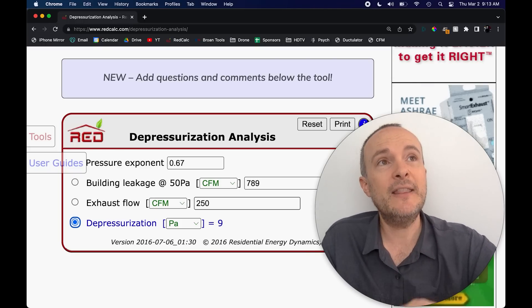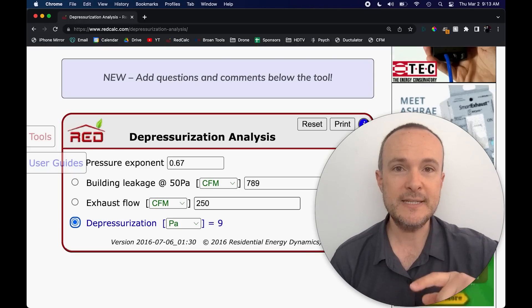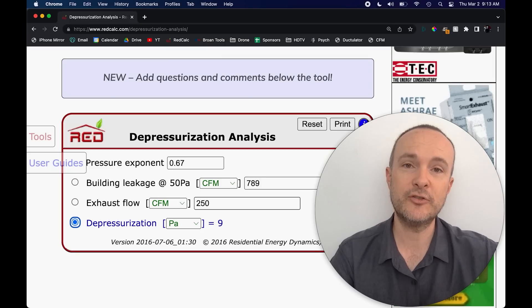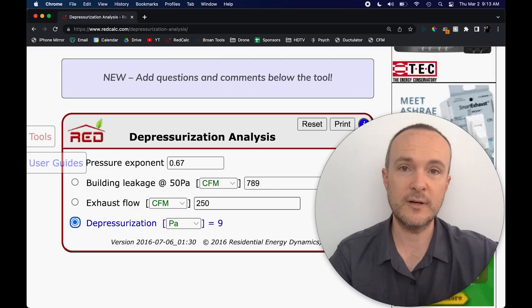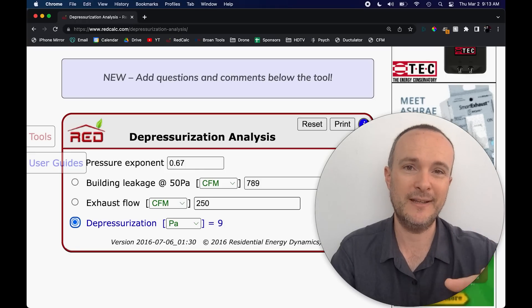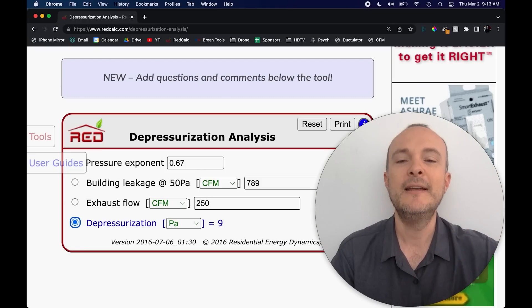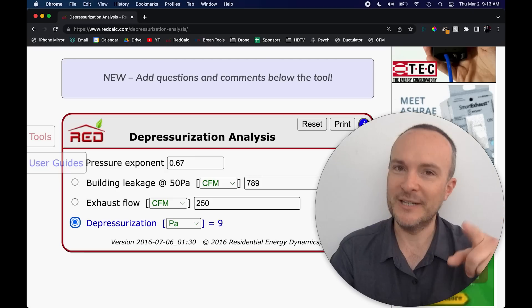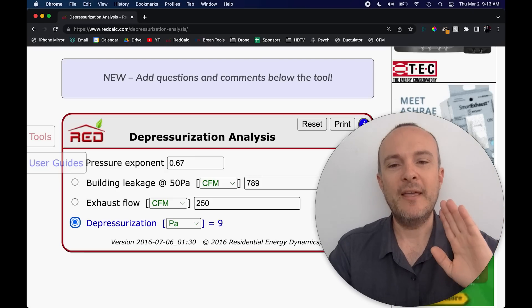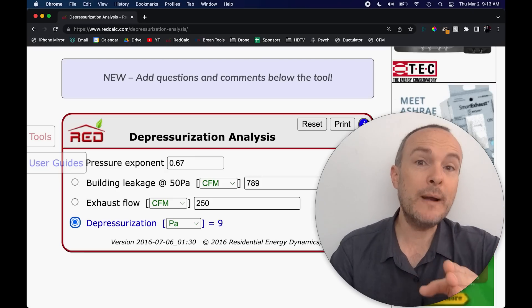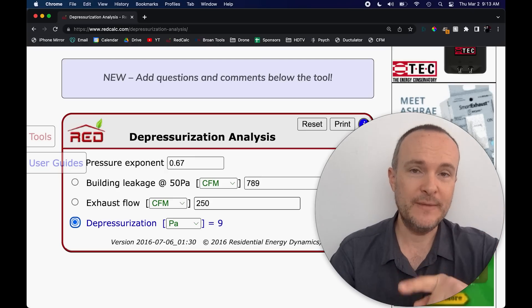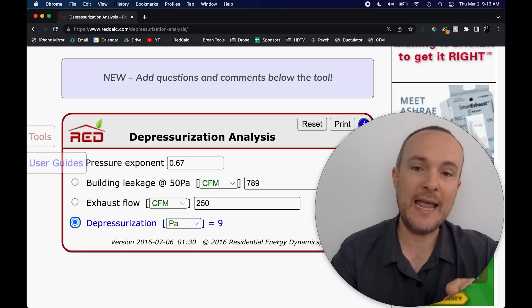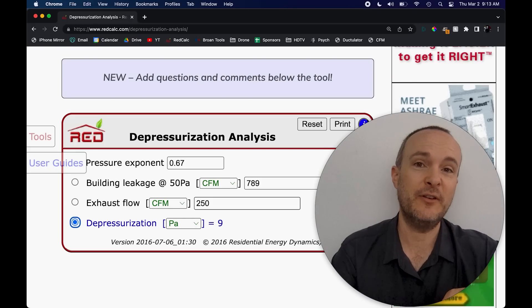Now, if we put all five of our exhaust fans on now, we're depressurized to almost 10 Pascals. This is a major problem. So I would say that in this home, given that it does not have a fireplace and it doesn't have any atmospheric draft water heaters or natural draft furnaces or anything like that, people are doing it just to be clear, but you shouldn't. Now we're at the point, this 1.5 ACH 50 in this home is where I would absolutely say we can't use these five 50 CFM exhaust fans.